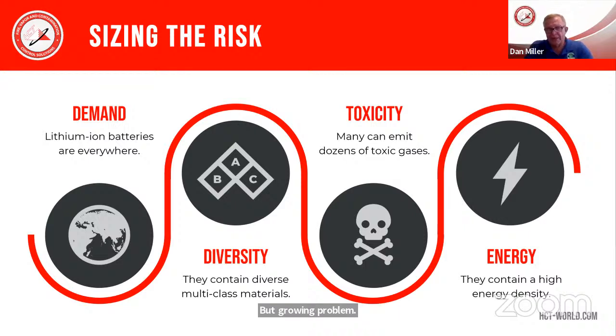There's a lot of diverse classes—at least five or six different popular types or chemistries of battery, like lithium iron phosphate, lithium manganese oxide, lithium cobalt oxide, and several others. Each one, when it breaks down and goes into thermal runaway, contains a different set of off-gases. But all of the off-gases are toxic, and all are flammable. So it doesn't really matter which battery chemistry is being used if it's putting off flammable and toxic gases and creating a high energy thermal runaway.